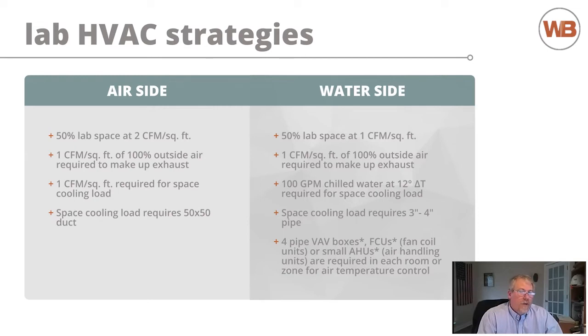And the interesting thing, when you start talking about the sensible heat gain of 1 CFM a square foot over 30,000 square feet, is that it's 30,000 CFM. Depending on the velocity you choose, you could be looking at a 50 inch by 50 inch duct, which is not insignificant in terms of riser, one, and for distribution on the floor too. So that's the airside baseline that maybe would have been used in a lot of cases by pharma and conversions in the past.